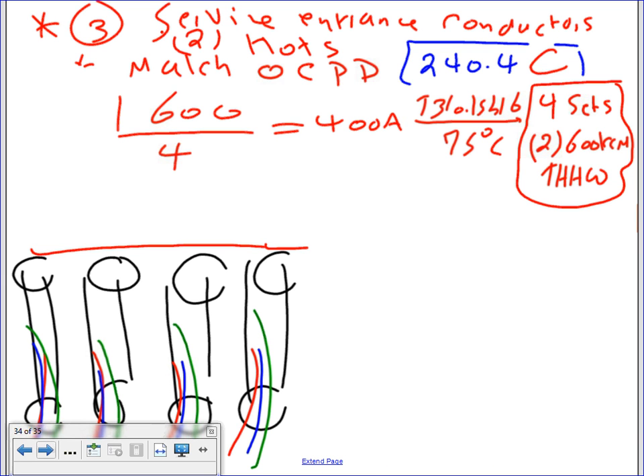Here are the 4 sets that I have. Why did I divide by 4? Because if I divide by 4, it gives you 400, and 400 gives me 600. That's a good size to pull. Can I divide it by 5? If I only do 5, what would that be? 1600 divided by 5 would probably give you 320, and 320 will give you 5 sets of 500. That's okay too. The reason I picked 4 here is that if you divide 1600 by 4, it's an easy, solid number. So you're going to end up with these 4 sets.